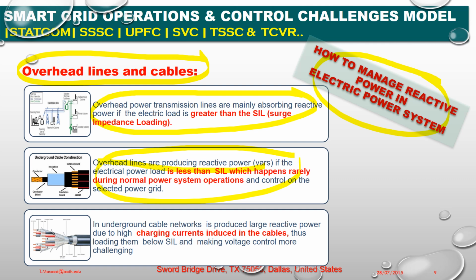Number 3, in an underground cable network a large amount of reactive power is produced due to the high charging current induced in the cables, thus loading them below SIL and making voltage control more challenging. That is important. So these are the 3 main factors which absorb and produce reactive power. In my next slide we will further discuss reactive power management.